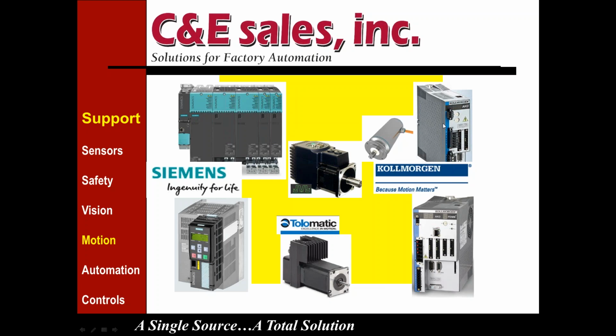To the right is a single axis servo drive from Kollmorgen, and you can see there their stainless steel servo motor that is one of the best in the industry, with a vented cable that goes all the way back to the panel, so when the motor's cooling off, it doesn't suck water in through the seals because it's vented all the way back to the panel for that temperature change. That's a single axis drive. Below that is a multi-axis controller from Kollmorgen that utilizes EtherCAT to connect to each of the drives downstream.